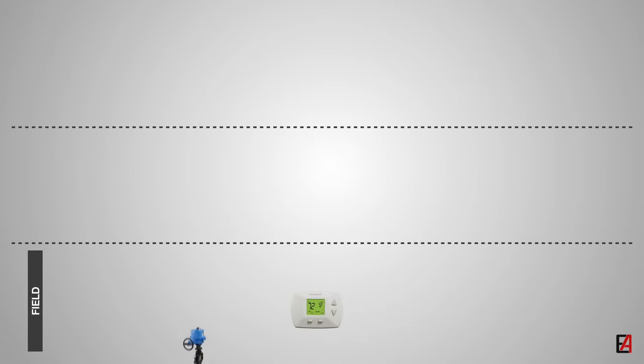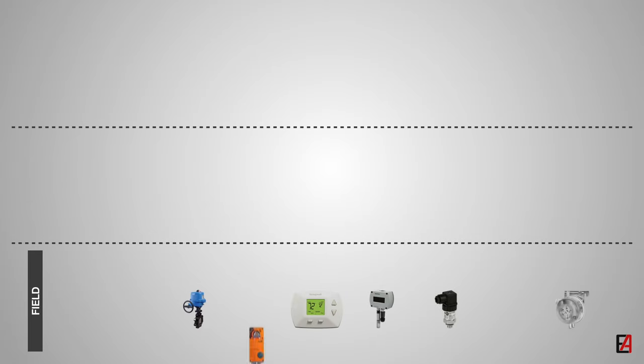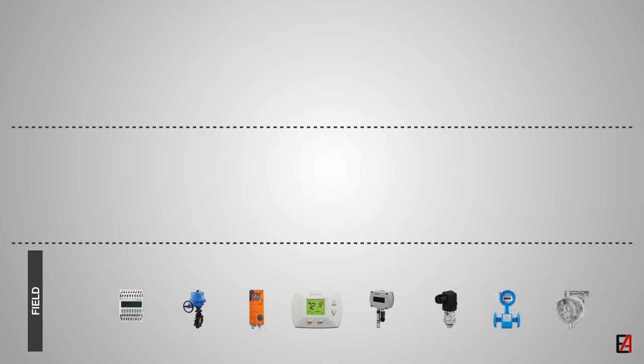The BMS system comprises three main levels. The first is the field level. This level refers to sensors, instruments, valves, actuators, thermostats, I/O modules, etc. This level plays an important role in the building management system, as the actions taken by the BMS system are purely based on the inputs received from this level.